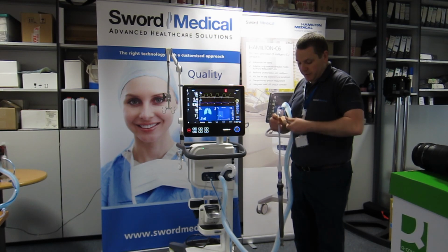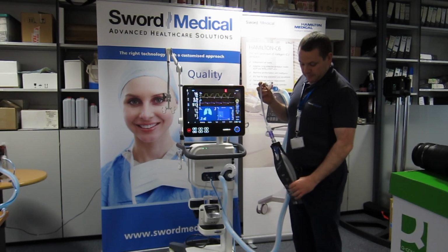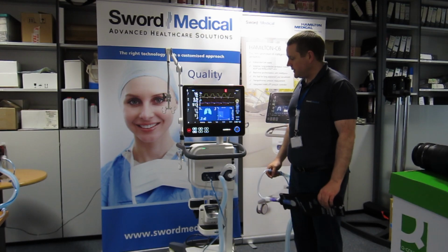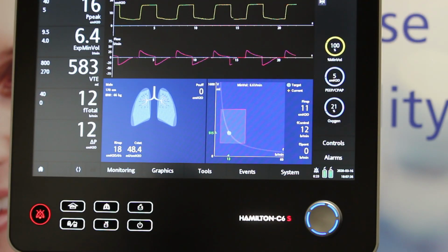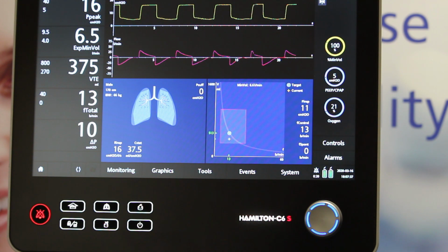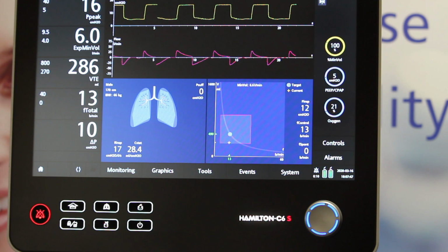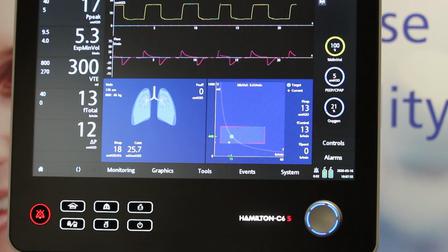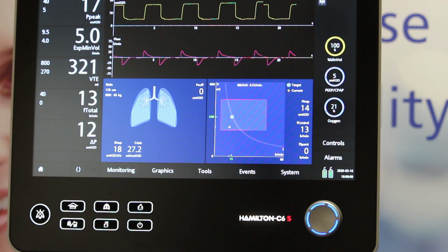So what I'm going to do is make the compliance really, really poor. So I'm going to hold on to my lung a little bit and just watch that compliance number deteriorate. So you can see my compliance is dropping down. My compliance number has now gone from 48 down to 28. And if you look at my ASV graph, my red box is starting to get longer. So you can see it's starting to increase the frequency and lower the tidal volume, which is what you would do with someone who's in respiratory distress.